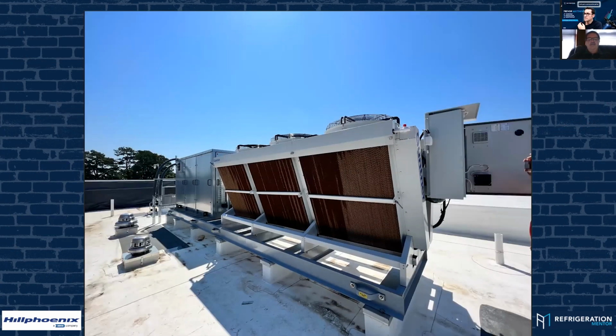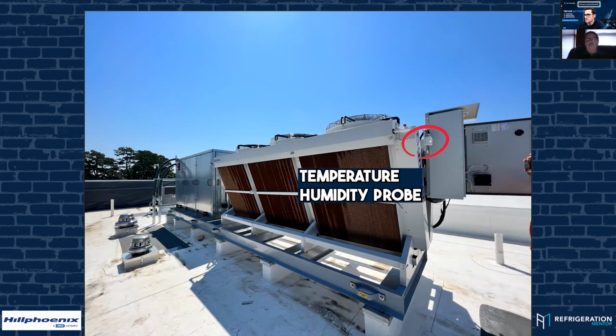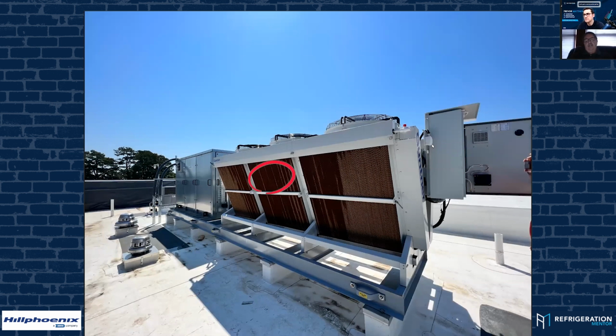So this is Güntner. For anybody who's not familiar with Güntner, this condenser does not have a pump system in it. What it has is a water meter and a modulating valve. So if you'll see right here up on the top right corner, that little white box near the control panel, that's the temperature humidity probe that the controller uses to determine the humidity and ambient temp sensor. And then on the middle side, on the left of the control panel, over here on the pads, you're going to have a temp sensor in there. You'll actually have two temp sensors in there, the one from the Güntner controller and our pad temp sensor. Because if we have an adiabatic condenser, we use a 10-degree approach. So that means there's going to be a difference of 10 degrees between the air entering and our liquid line.